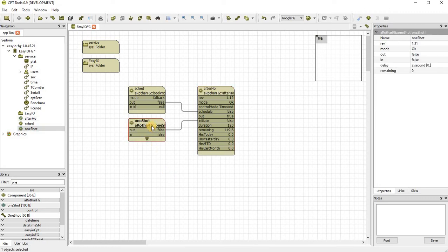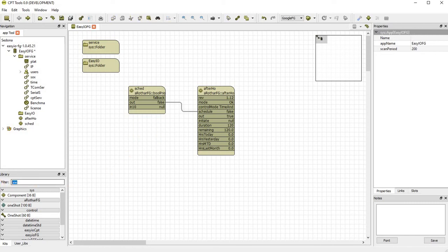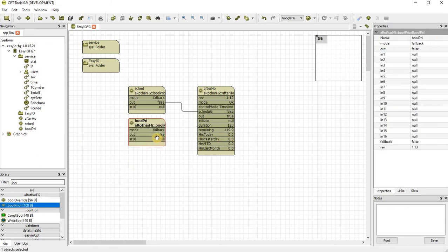If we set our timer for reset time, then when we press the after hours button, it will reset the remaining time back to 120 minutes and then start counting down again. If you had a light switch or some kind of toggle switch rather than a momentary switch initiating the system, just turn our schedule on to cancel the timer. Turn it on, you silly duffer.